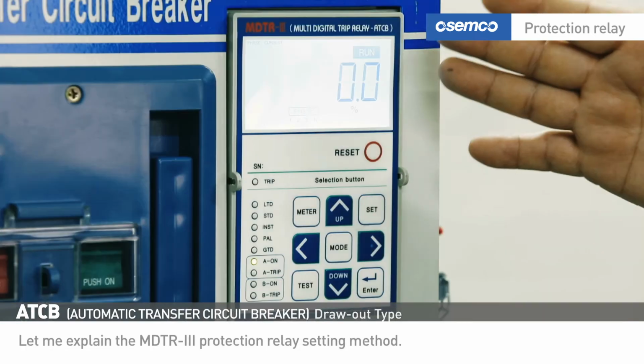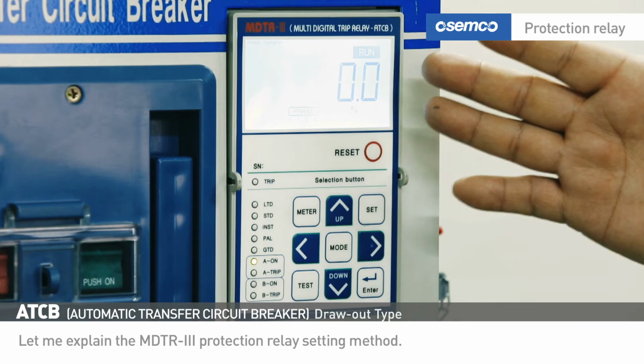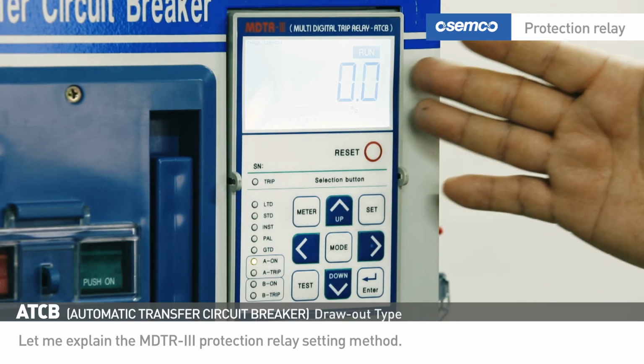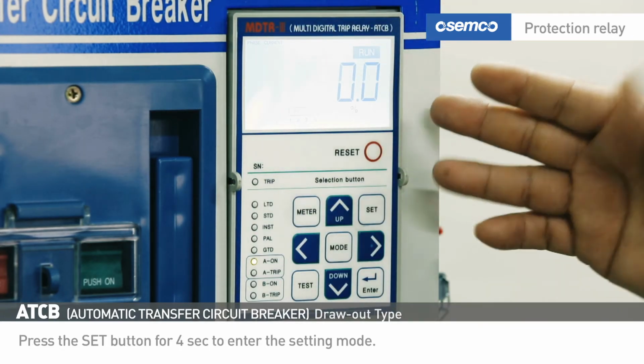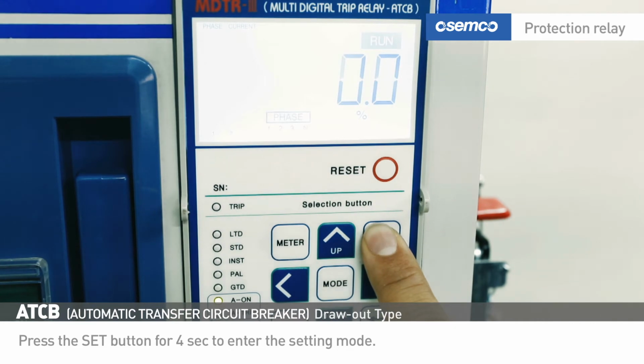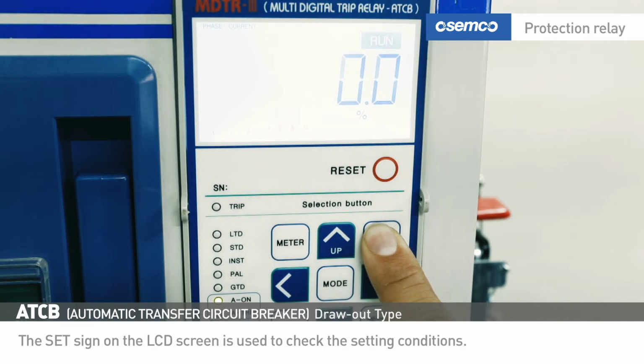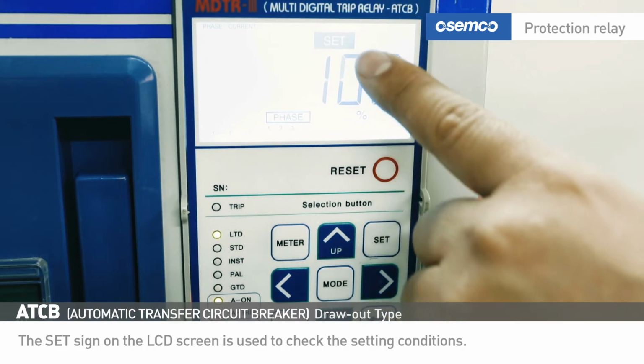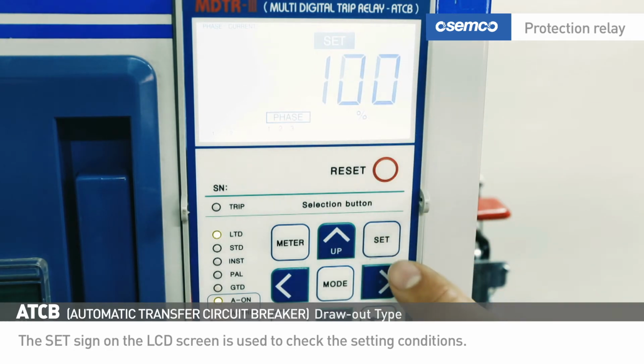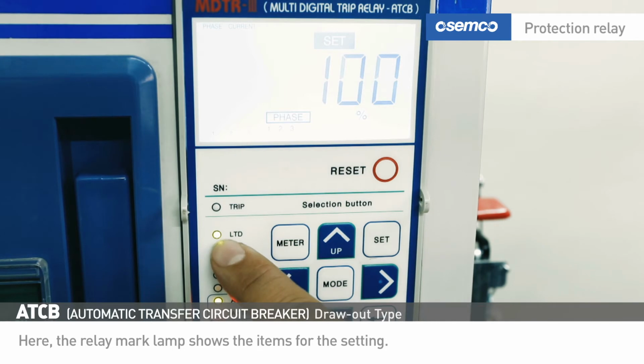Let me explain the MDTR3 protection relay setting method. Press the Set button for 4 seconds to enter the setting mode. The Set sign on the LCD screen is used to check the setting conditions. Here, the relay mark lamp shows the items for the setting.